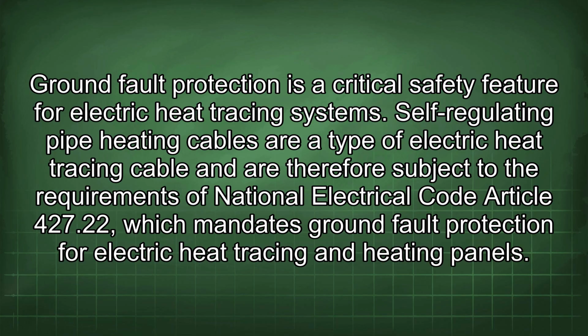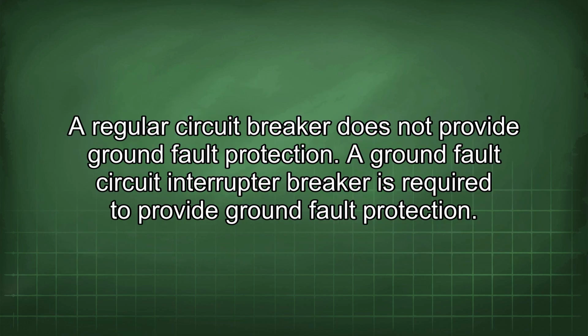Ground fault protection is a critical safety feature for electric heat tracing systems. Self-regulating pipe heating cables are a type of electric heat tracing cable and are therefore subject to the requirements of National Electrical Code Article 427.22, which mandates ground fault protection for electric heat tracing and heating panels. A regular circuit breaker does not provide ground fault protection. A ground fault circuit interrupter breaker is required to provide ground fault protection.